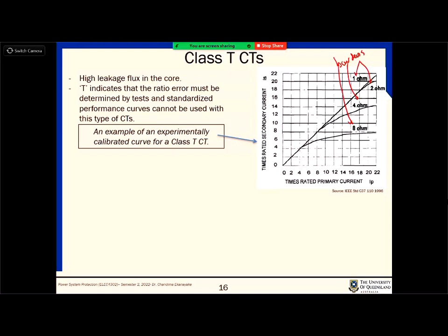Right? That is the impedance connected to the secondary circuit. Can you see now the characteristics change with the burden? If you increase the resistance in the secondary circuit, the transformer or the CT goes into the saturation region very quickly. But if you have a very low impedance in the secondary circuit, you can maintain the linearity. Right? So that is why the secondary burden is very important when you are dealing with a CT.